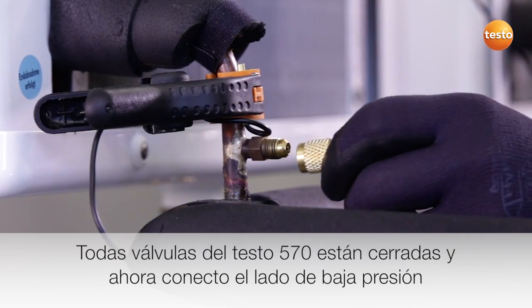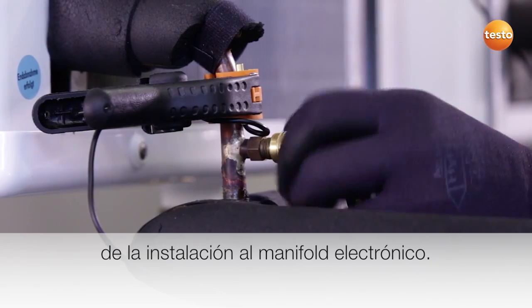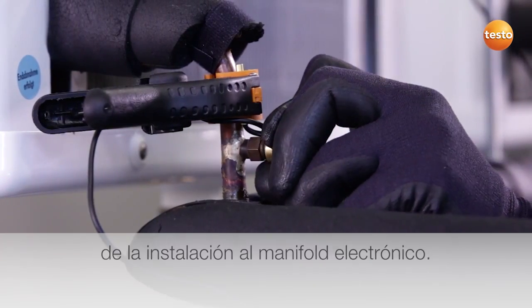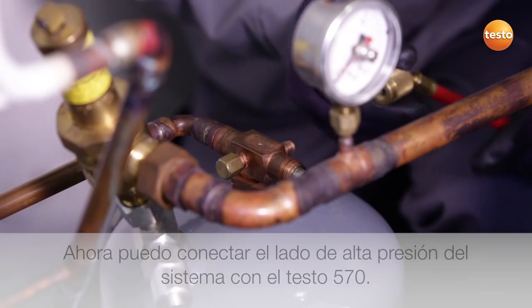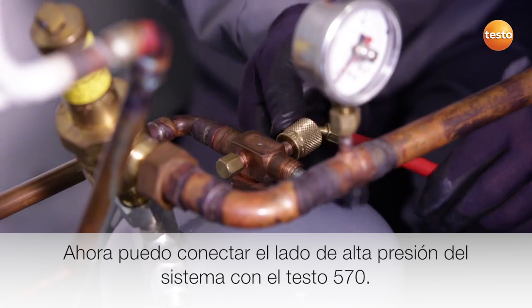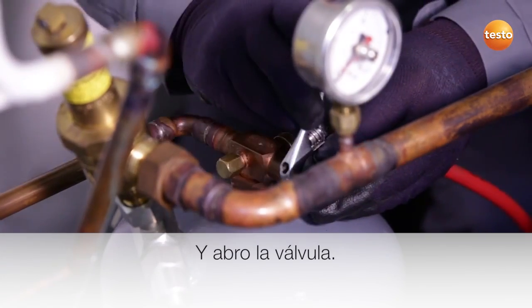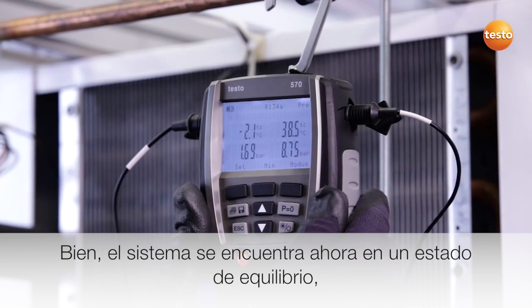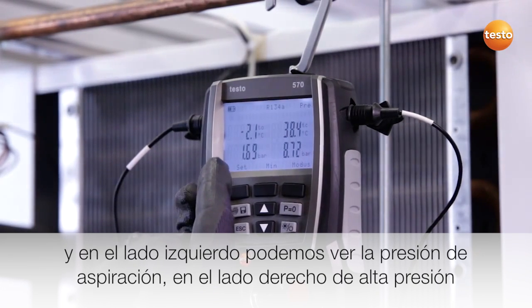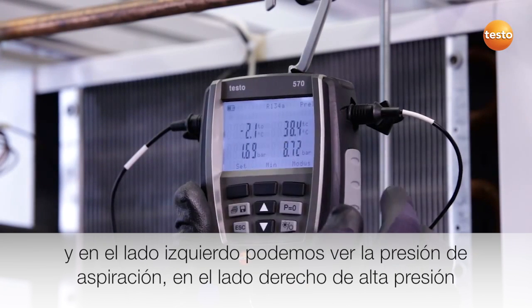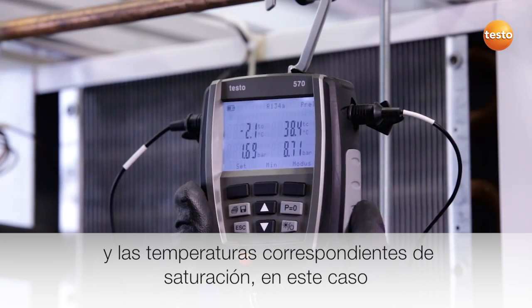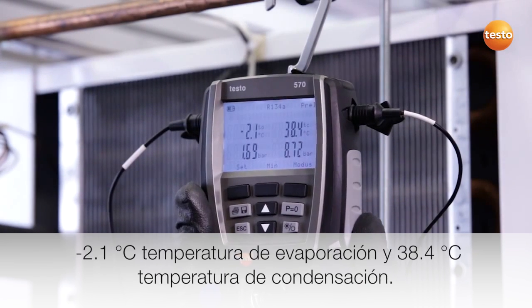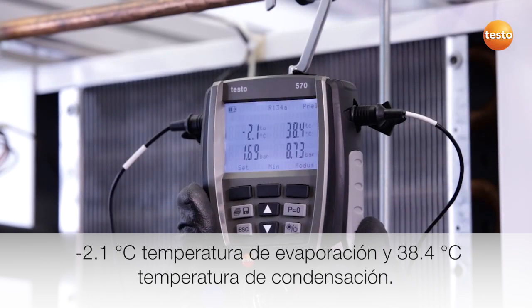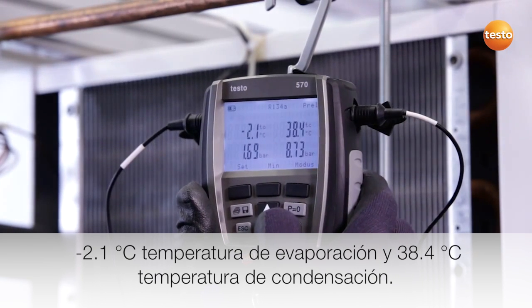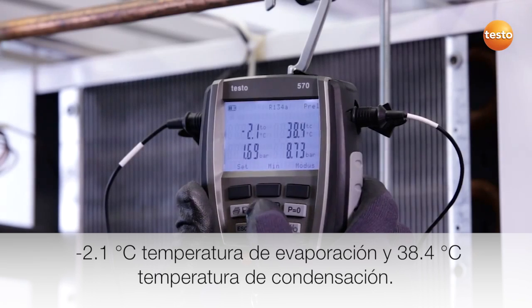All valves on the manifold are closed, and I now connect the low pressure side of the system to the instrument. I now connect the high pressure side of the system to the manifold and open the valve. Okay, the system is now in a steady state, and on the left-hand side we can see our suction pressure. On the right-hand side, the high pressure and the corresponding saturation temperatures, in this case minus 2.1 degrees Celsius evaporation temperature and 38.4 degrees Celsius condensation temperature.